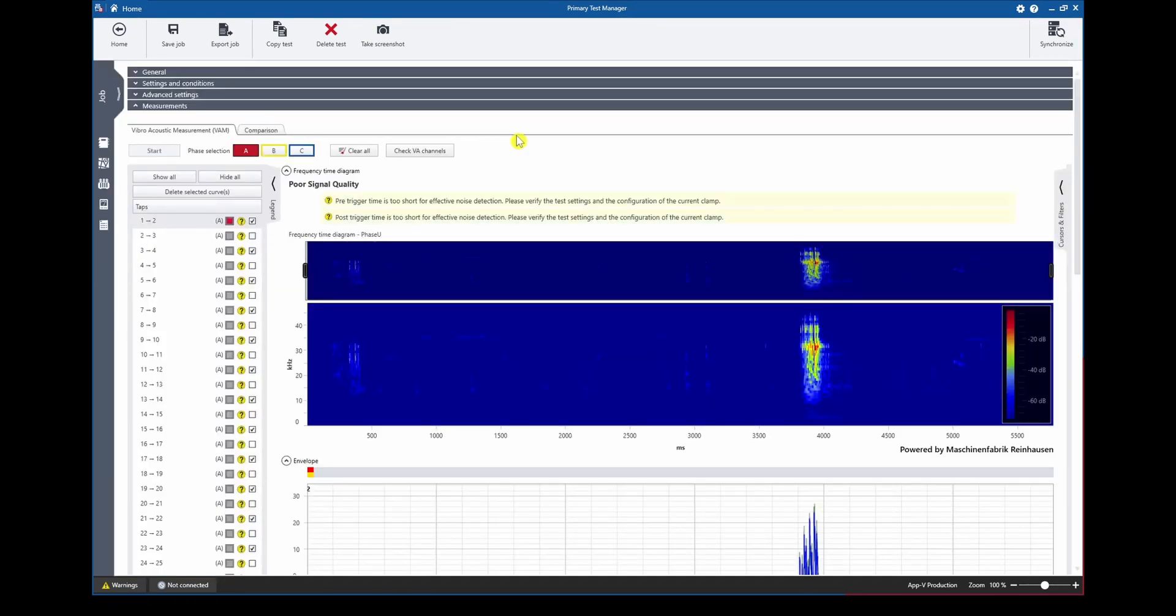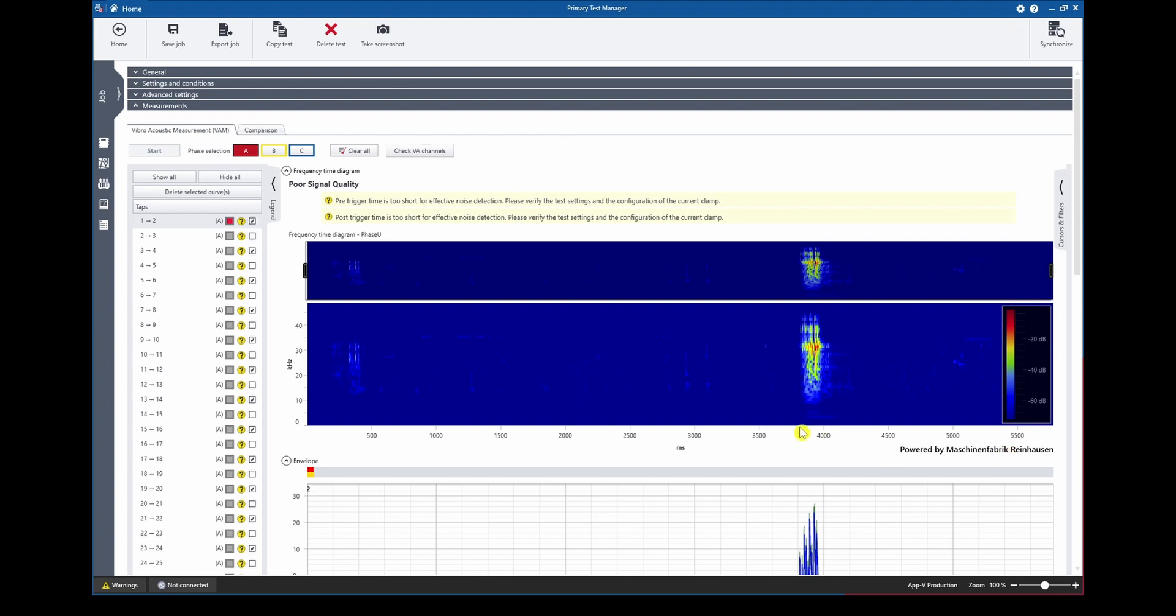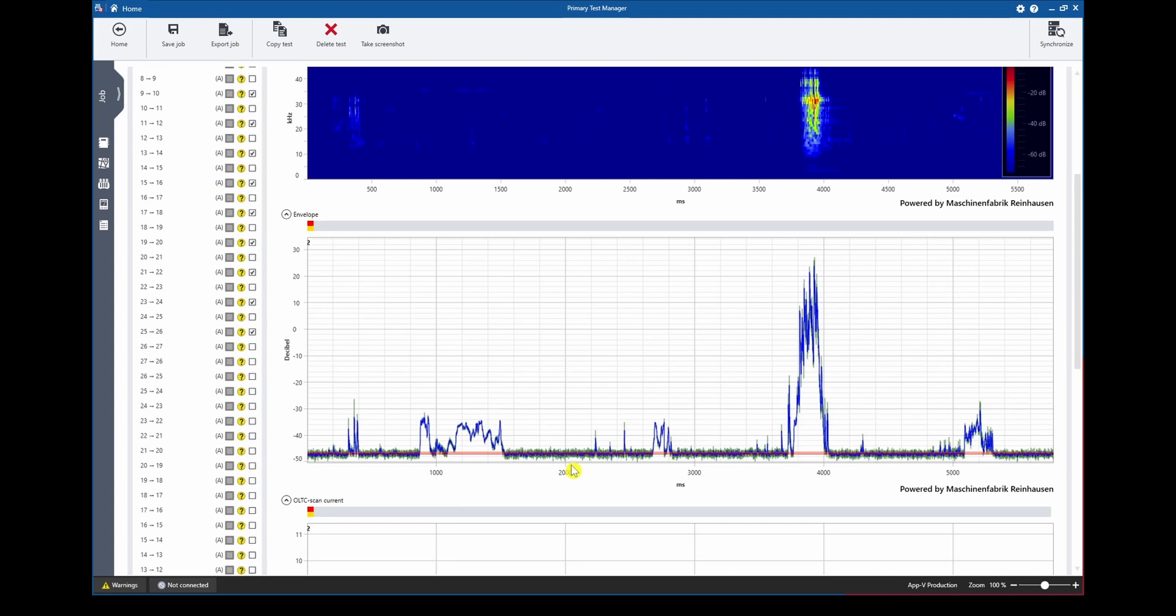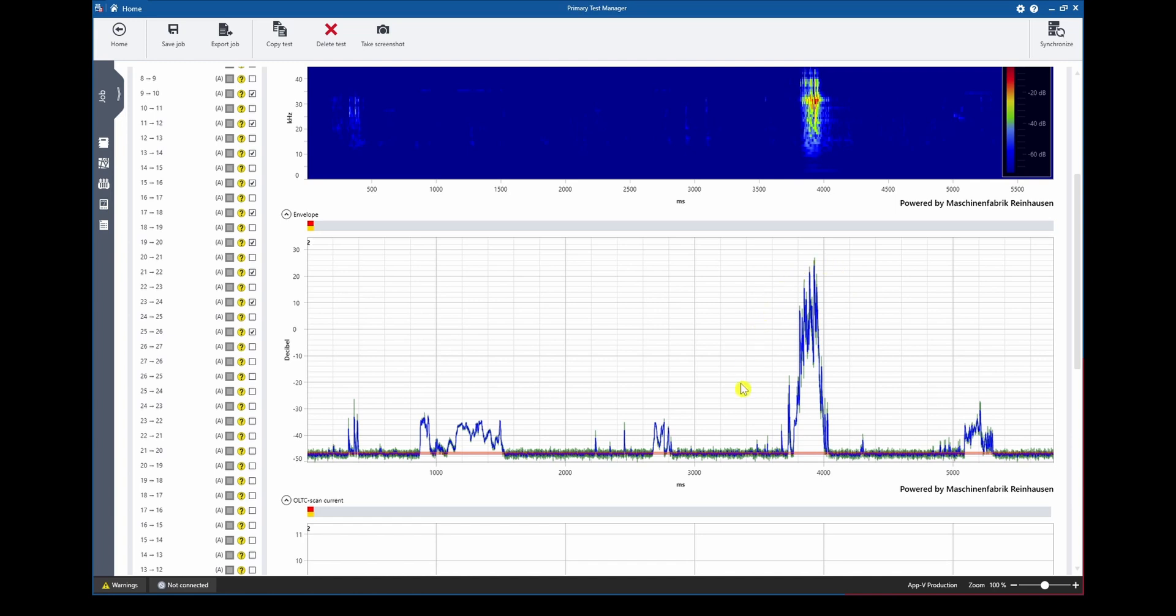Inside the measurement tab for each recorded tap curve four diagrams are shown. The first one is the frequency time diagram which shows the frequency content over the whole signal recording time and by using this color coding we can identify areas of high signal activity. The second one which is used for comparison and the main curve for analysis is the so-called envelope curve. It will show basically the energy of the signal during the whole recording time, indicating here for example the diverter switch operation.